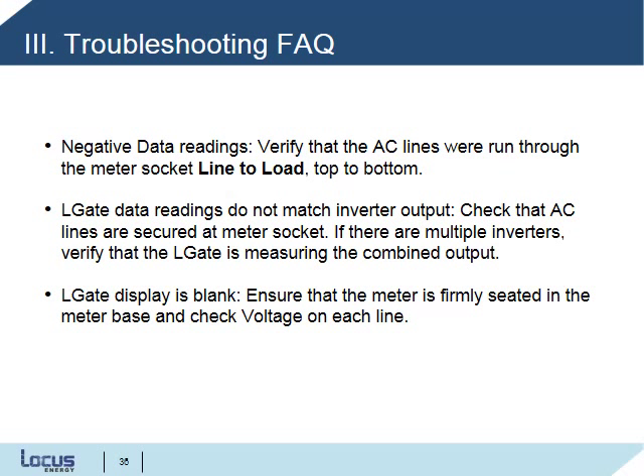During the site commissioning process, there are a few common issues that may arise. Here are a few troubleshooting steps to follow if you encounter any of these issues. The first potential issue is that we're receiving negative data readings from the LGate. We recommend verifying that the AC lines were run through the meter socket line to load, top to bottom, and checking that the arrow on the LCD screen is pointing to the right, not to the left.